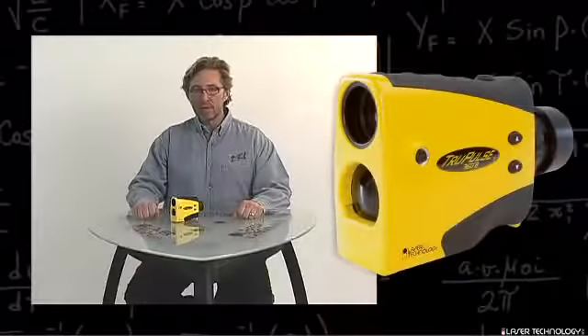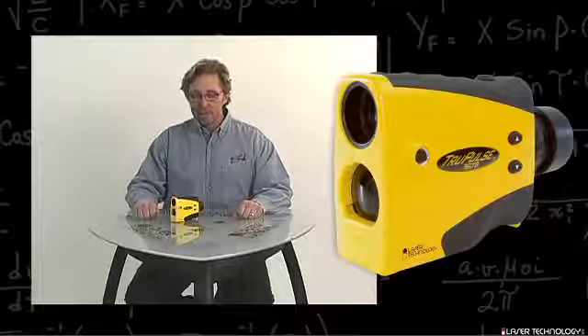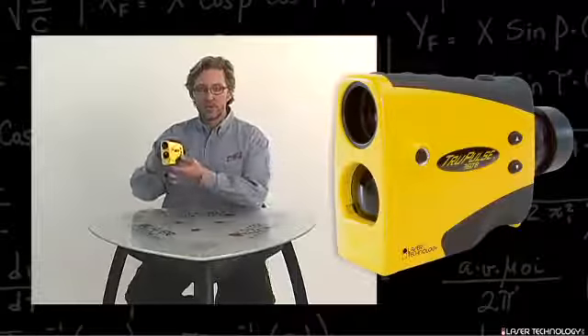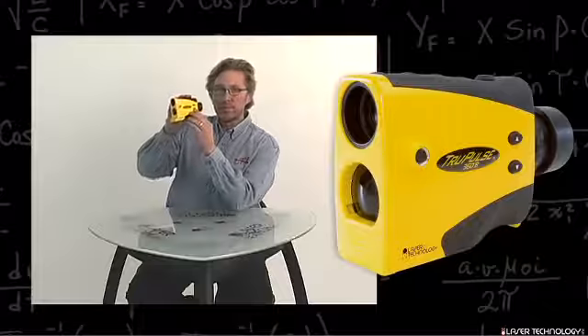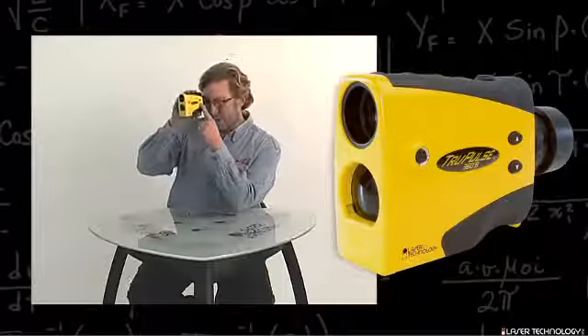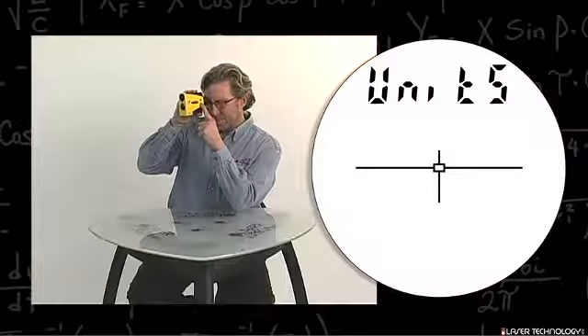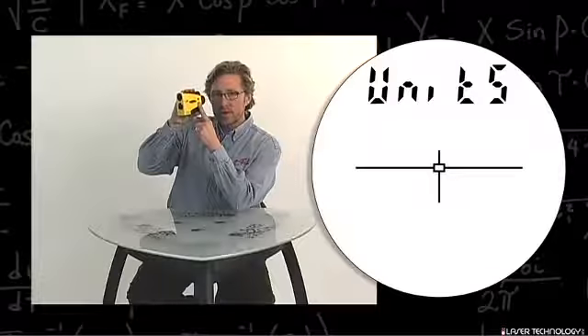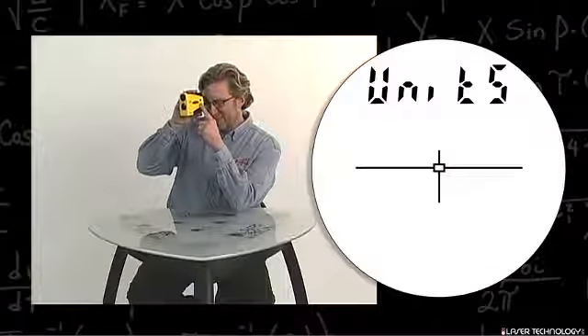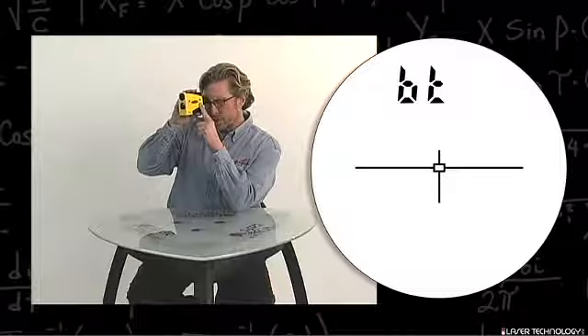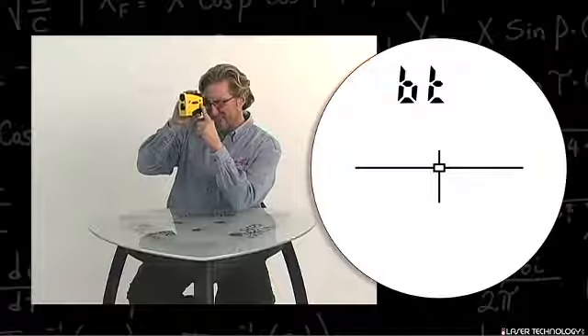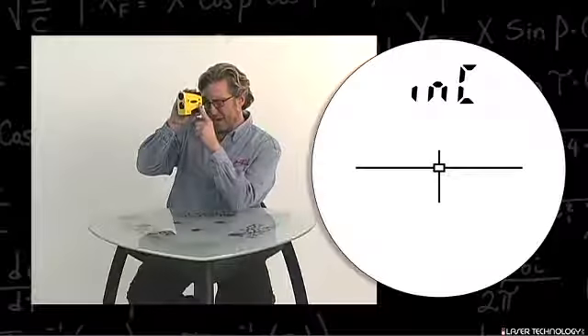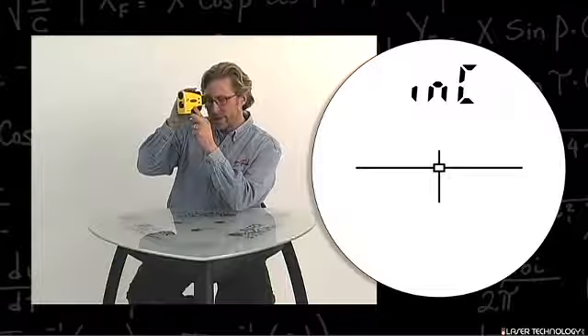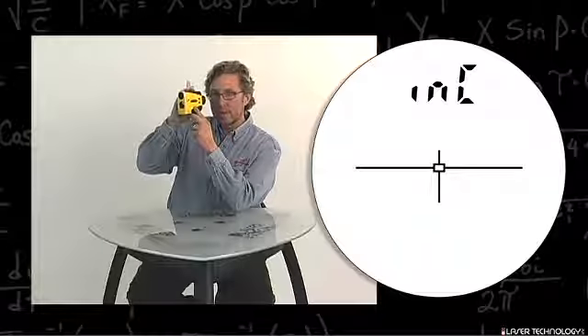This is the calibration routine for the tilt sensor. The first step that we're going to do to get into the sensor routine is you do a long press on the down arrow. What will come up is the word units at the top of the screen. Hit your down arrow one time, it'll scroll to BT for Bluetooth. Hit your down arrow one time and it will say INC for inclination. This is where the calibration routine is.